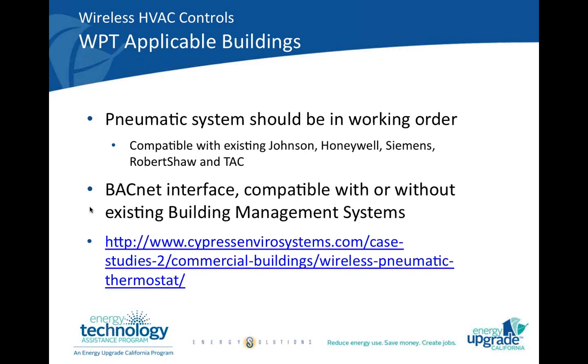So where should you look if you're looking at WPTs? A building needs to have a pneumatic system, and it should be in working order, no concerns about leaks, etc. WPTs are compatible with a wide range of existing pneumatic systems, Johnson, Honeywell, Siemens, Robert Shaw, etc., as you see on the screen there.